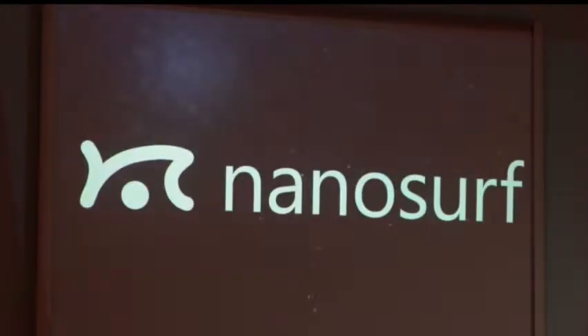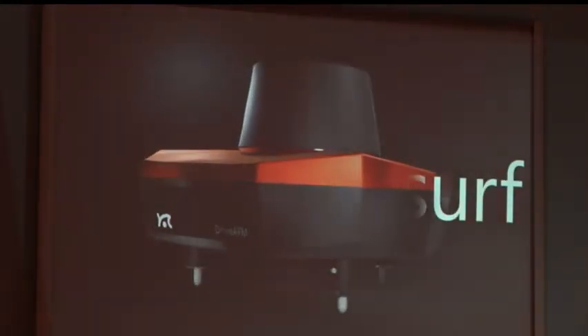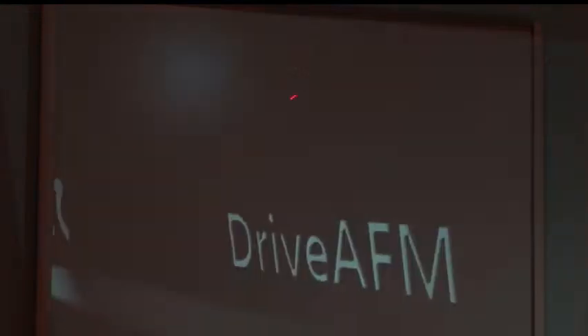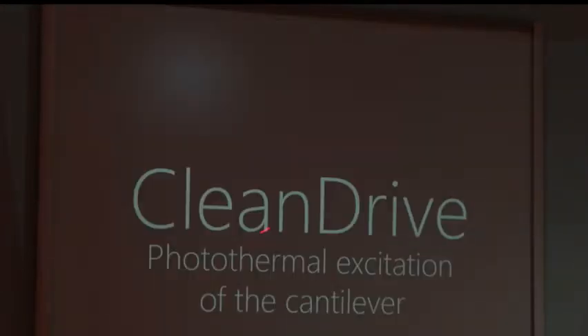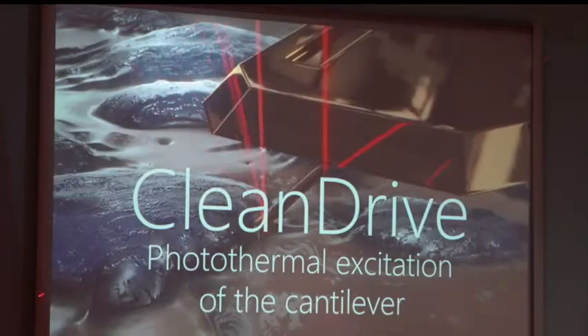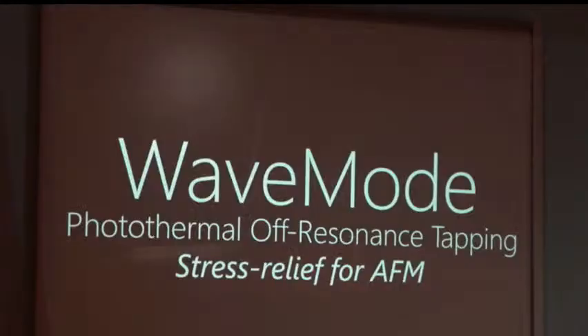This is how the Nanosurf DriveAFM looks like. On top, you have the camera, and the whole part is like this. This is your cantilever holder. It also comes with a new technology where a second laser falls on the cantilever, which excites the cantilever so that you can image everything quite nicely in liquid without having multiple peaks.